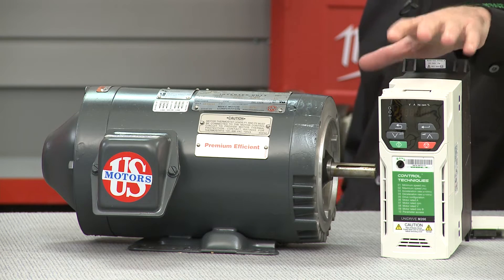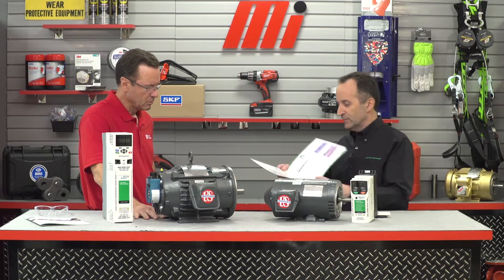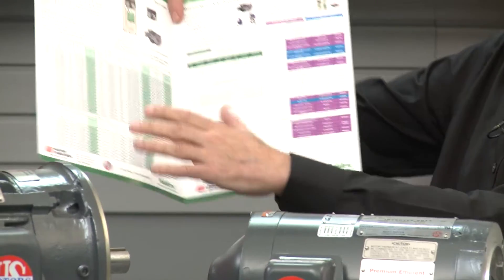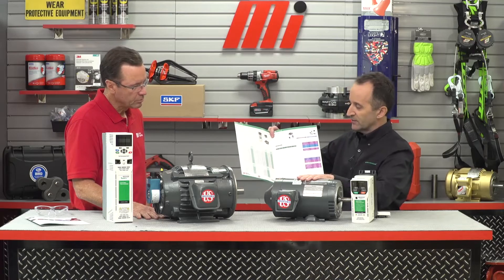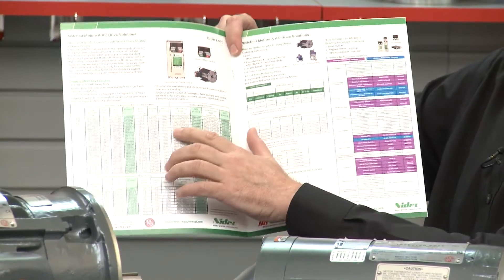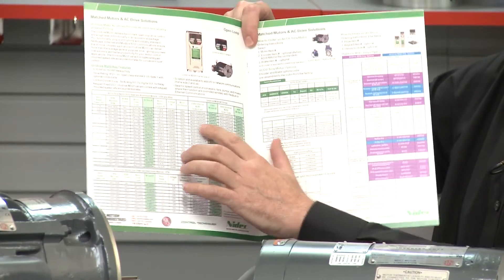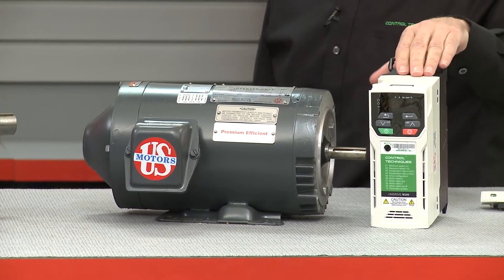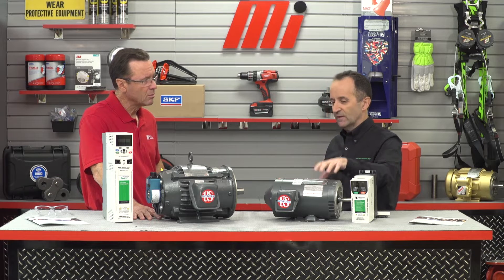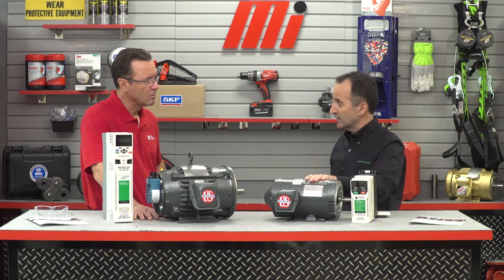Our most popular model is this Unidrive M200 VFD. To make life easy, we've created a simple selection flyer which has matched motors and VFDs. Once you've selected your motor, you look across the row and pick the appropriate VFD based on voltage. In this case we have a 3.4 amp motor and a 4.2 amp VFD, so this combination will work. An important note: to get the best value, always work off of the motor nameplate current and size the VFD on that rather than motor horsepower.